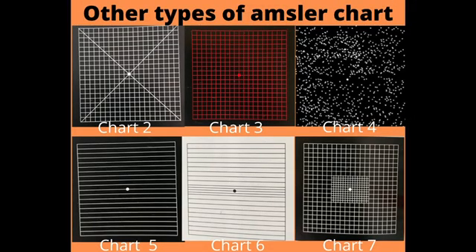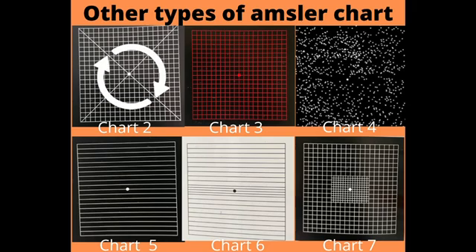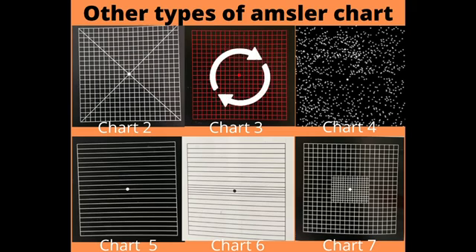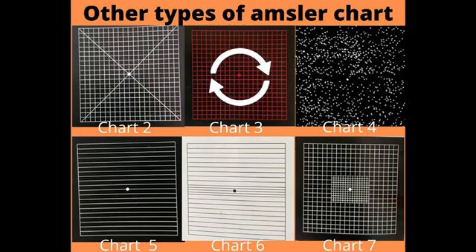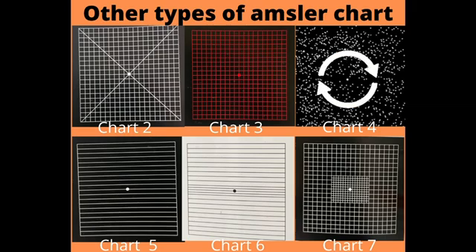There are seven chart types in total. Chart 2 is similar to chart 1 but has diagonal lines that aid fixation in patients unable to see the central spot as a result of a central scotoma. Chart 3 is identical to chart 1 or 2 but has red squares; it is used to detect color scotomas and desaturations that may occur in toxic maculopathies, optic neuropathies, and chiasmal lesions. Chart 4 consists of only random dots and is used mainly to distinguish scotoma from metamorphopsia.